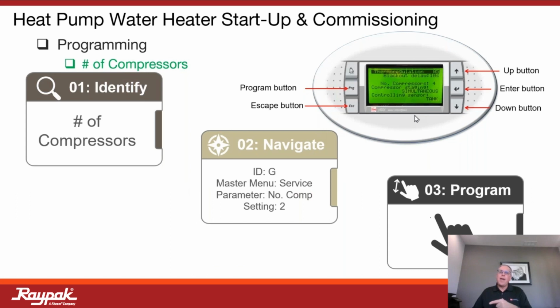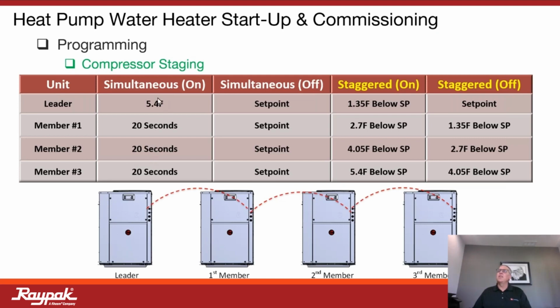Also on this screen, I'm backing up here again. Here's where that default was simultaneous. And this again is the type of cascade that we're talking about. Well, what does that mean? Well, here's what that means. The default is simultaneous, and the default differential, as we said, was 5.4 degrees. Here I'm just illustrating a scenario where I have 4 heat pumps in a sequence.